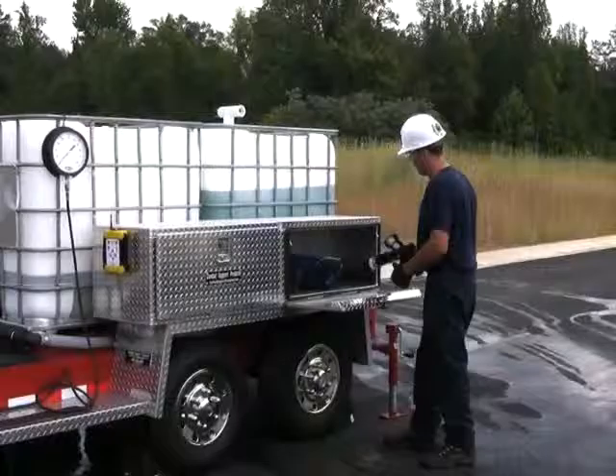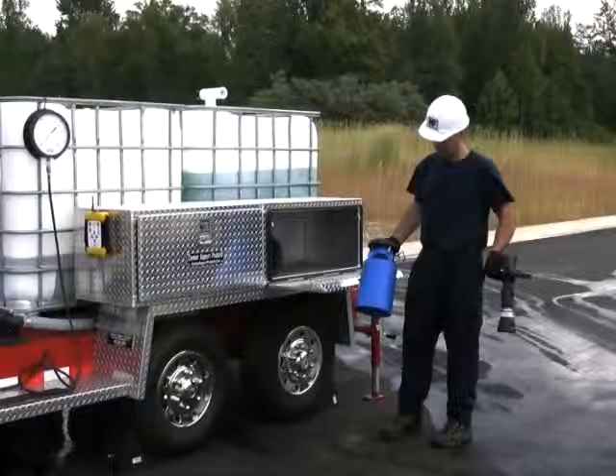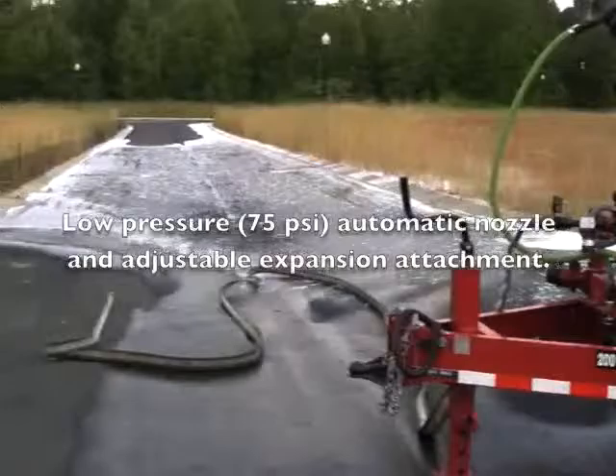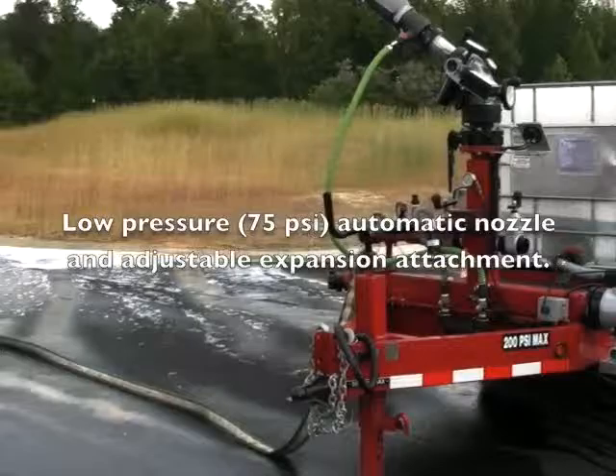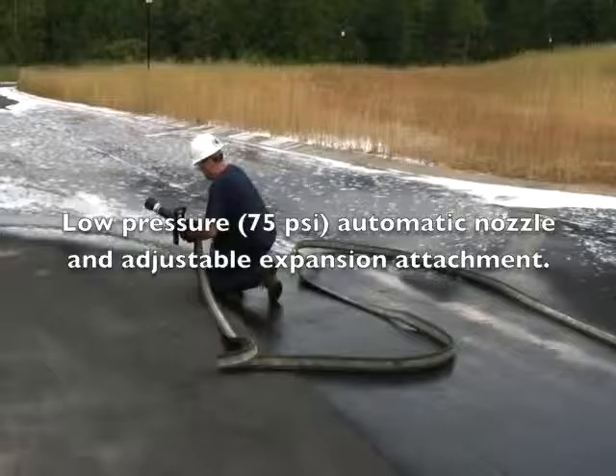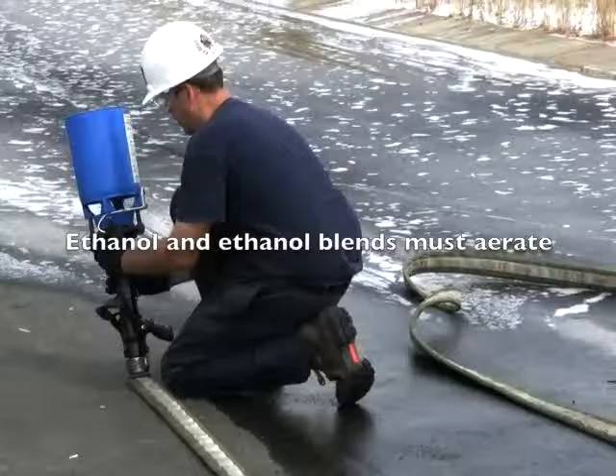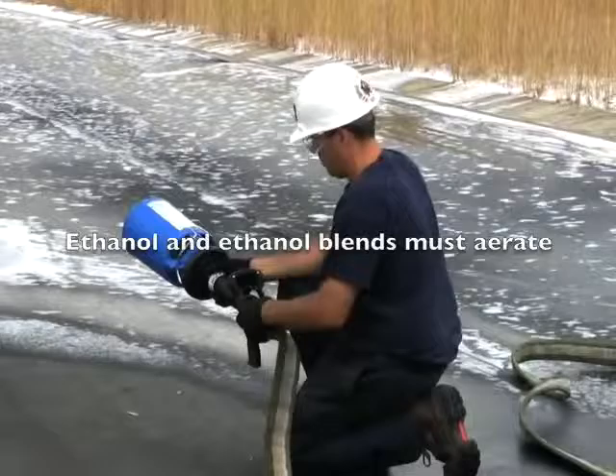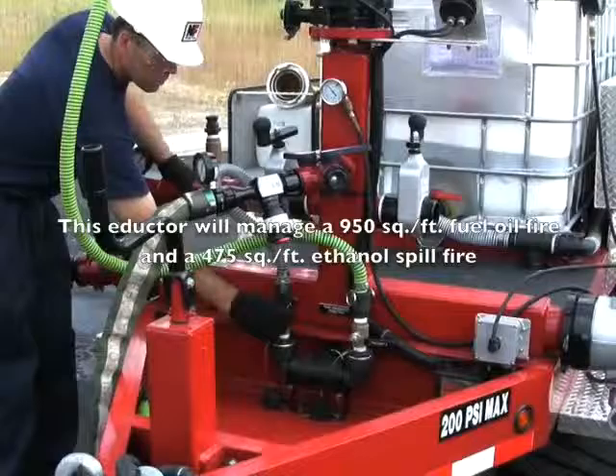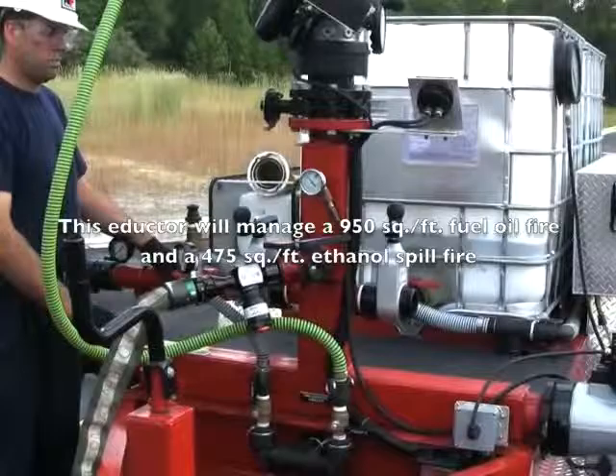What we're going to do now is go to the hand-line operation. We're going to take a low-pressure 75 PSI TFT mid-force nozzle and the matching MX foam jet attachment for it and make it fast to the end of this hose. For the sake of this training exercise, we're only using 50 feet of hose. We can go 300 feet between the foam eductor outlet and the nozzle inlet using inch and three-quarter hose and a 75 PSI nozzle. Dan is going to attach the MX foam jet attachment to the nozzle. Whenever we're dealing with alcohols, polar solvents, blended gasoline — particularly E85 — there is no getting around it: you have to use aerating equipment.